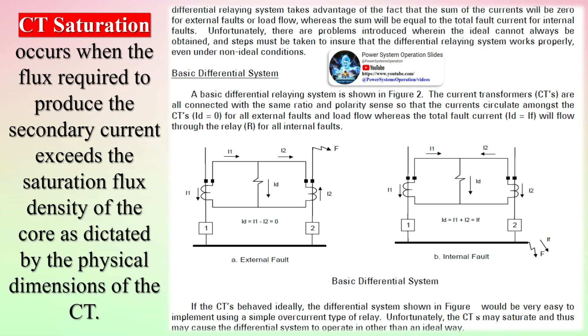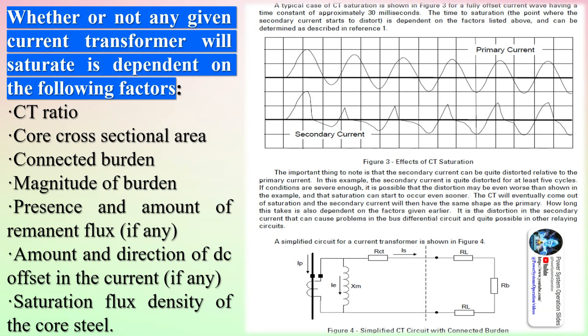Kirchhoff's current law states that the sum of the currents entering a given node must be equal to the currents leaving that node. For the case of an external fault, the current leaving the bus is equal to the sum of all of the currents entering the bus, and the total summation is zero. The same would be true when considering load flow. For the case of an internal fault, the sum of all of the currents entering the bus equals the total fault current — the summation is not zero.